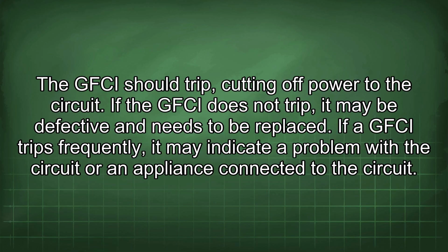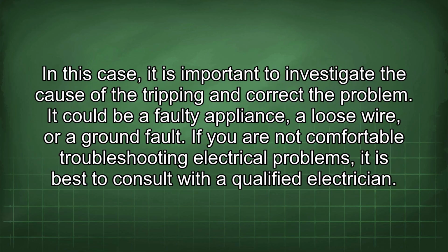If a GFCI trips frequently, it may indicate a problem with the circuit or an appliance connected to the circuit. In this case, it is important to investigate the cause of the tripping and correct the problem. It could be a faulty appliance, a loose wire, or a ground fault. If you are not comfortable troubleshooting electrical problems, it is best to consult with a qualified electrician.